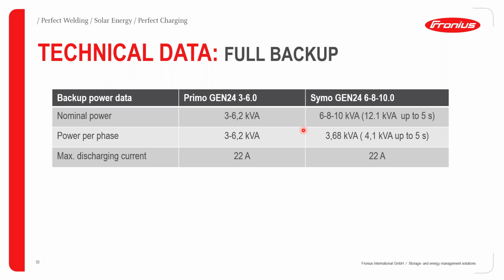So with this, the nominal power per phase ranges for the Primo, as said earlier, from 3 to 6.2 kVA. For the Symo, it ranges up to 12.1 kVA for up to 5 seconds to handle transient loads. Then power per phase is 3 to 6 for the Primo, and up to 4.1 kilowatts for up to 5 seconds to handle transient surges. So, of course, the maximum discharge current for both cases is 22 amps.